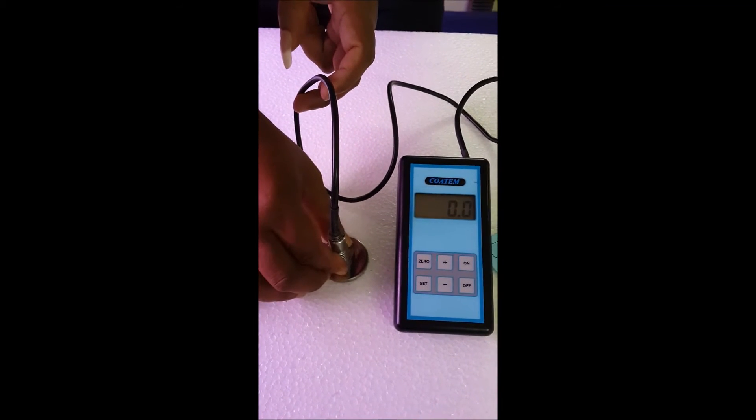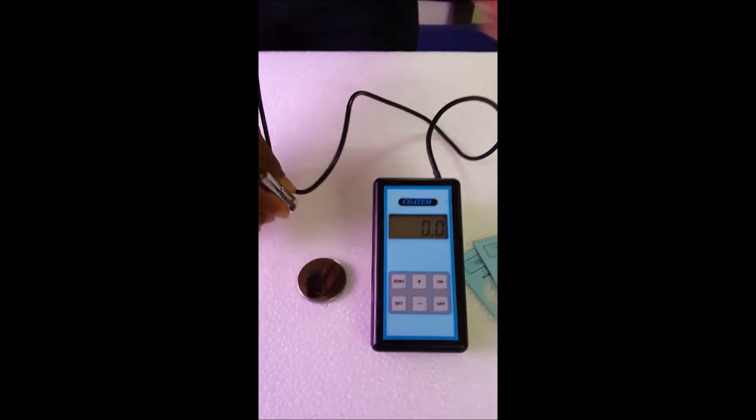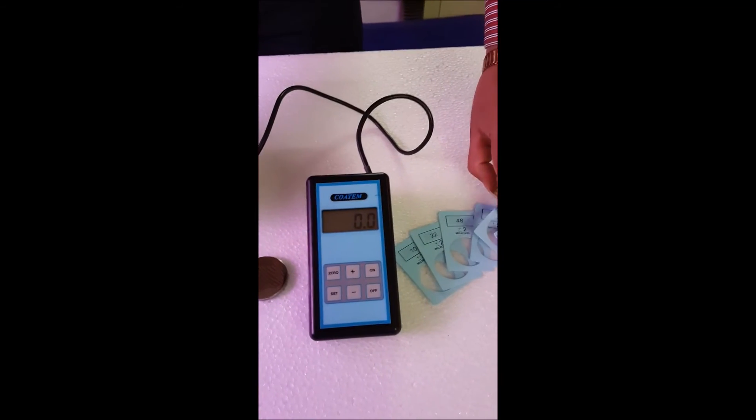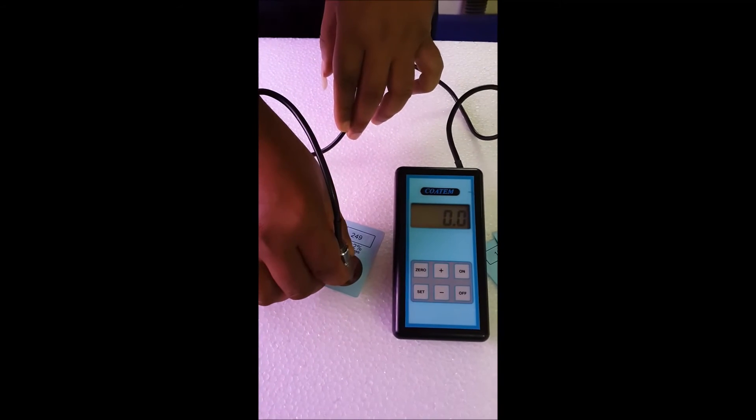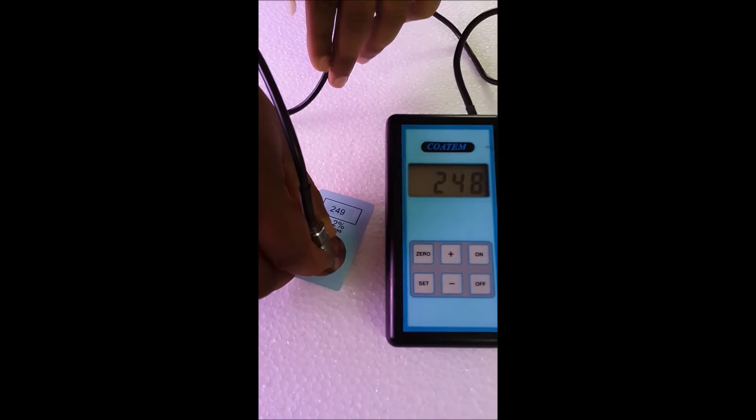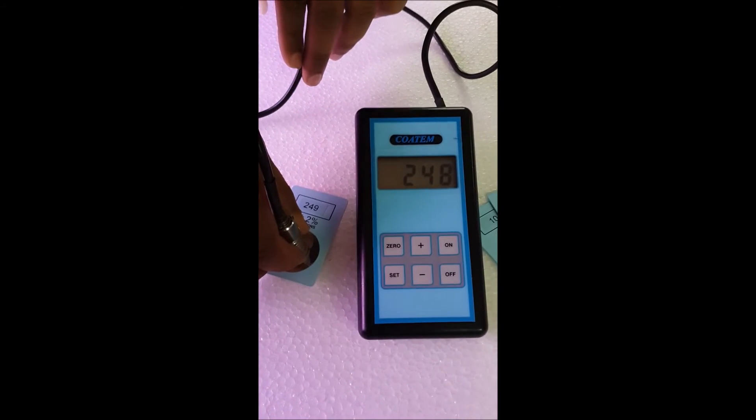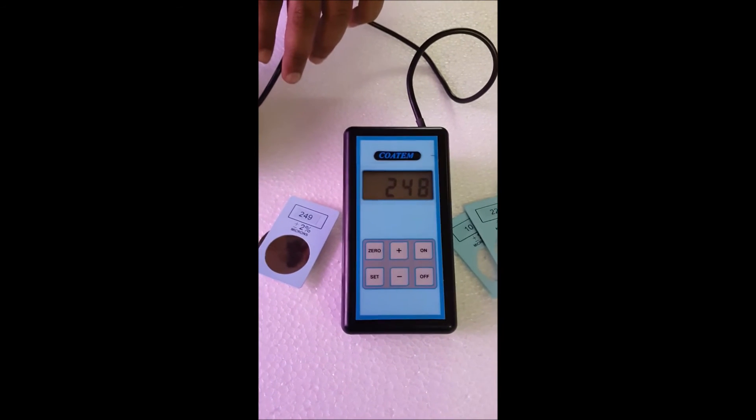Place the probe on the zero block and you get zero. That's fine. Now we take the calibration strip and check. 249. Okay, the instrument is working fine.